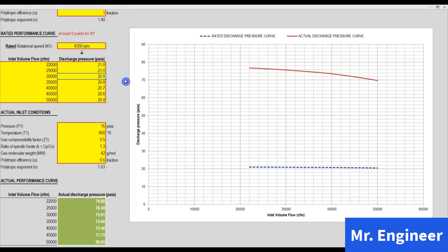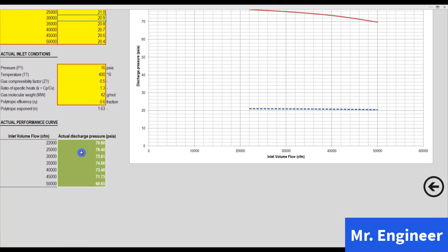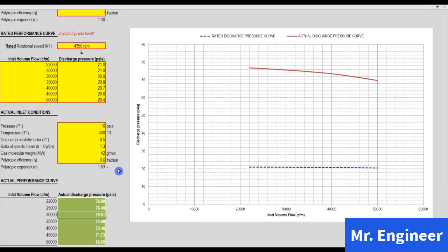Under the new and actual inlet conditions, for 30,000 cubic feet per minute, the compressor will develop a discharge pressure of 75.6 psi. So, as you can see here, the compressor performance in terms of discharge pressure is heavily dependent on inlet conditions. Any deviation from the rated inlet conditions will result in a discharge pressure different from what can be expected from the performance curve.